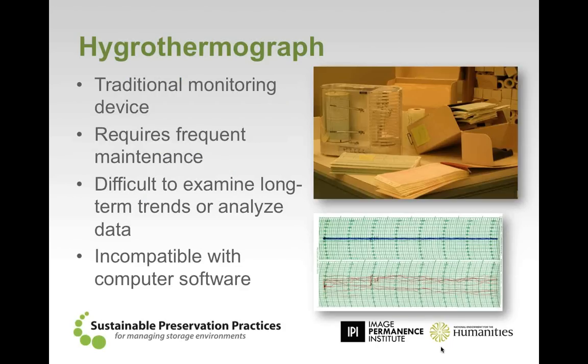One of these tools I like to bring up is the hygrothermograph. It's an excellent tool. It's been around for nearly 200 years. There's a lot of people that still use these, and I'm actually surprised when you realize that the cost of one of these hygrothermographs is probably about 3 quality digital data loggers. So they're rather expensive, and they require frequent maintenance: the pens, the papers, calibration, and depending on whether it's plugged in, they require batteries.